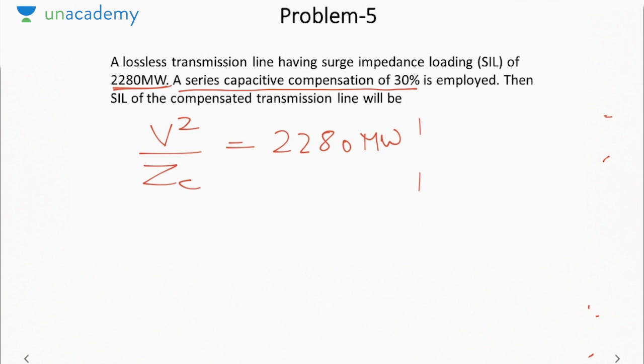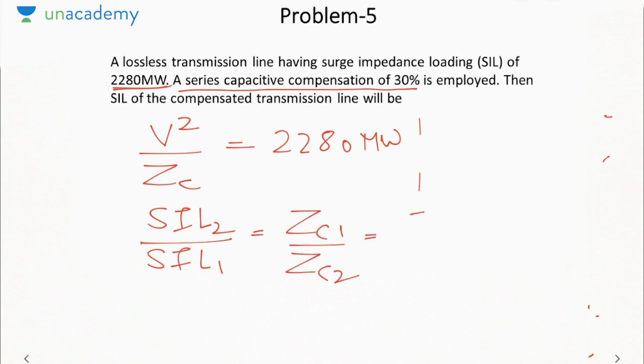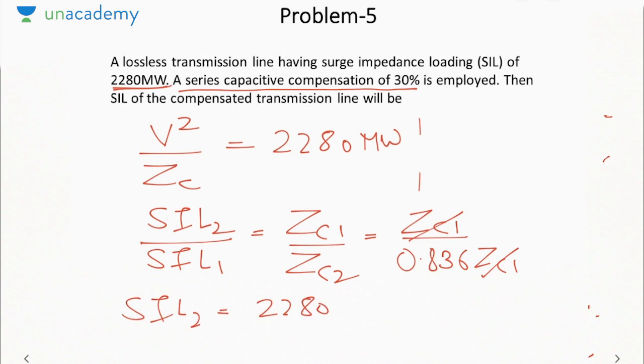So what I will write is SIL2 by SIL1 is ZC1 by ZC2, that is ZC1 by 0.836 ZC1. So SIL2 will be 2280 by 0.836, so it is 2725 megawatt. So the surge impedance loading increases in case of a series capacitive compensation. Okay.